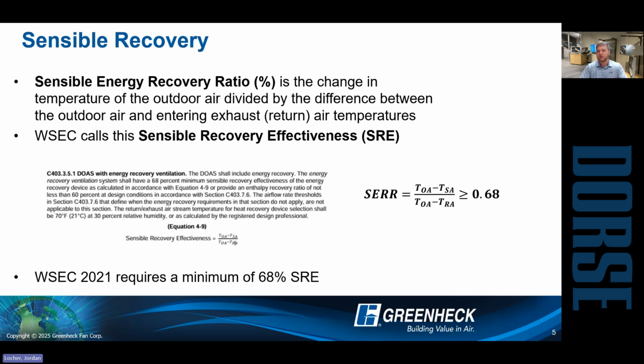And really, there's few and far between situations where you need to have sensible only, right? So there's a lot of misconceptions out there that, for some reason, I can't use ERR or ERV, right? It's not really true. The big thing too is, these are still exhaust fans. You're still going to be exhausting moisture from the space. It's just not as big of a concern in a milder climate. So for Greenheck, we promote using ERR enthalpy recovery. However, that sensible recovery metric can be used as well.